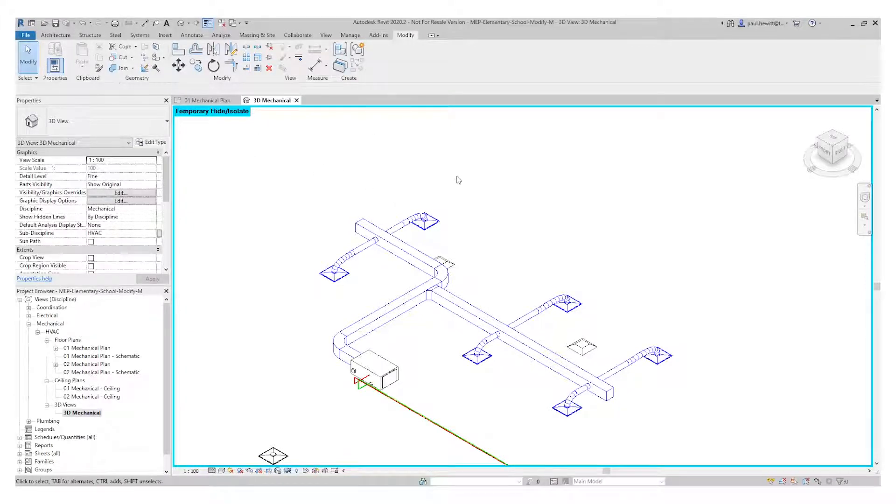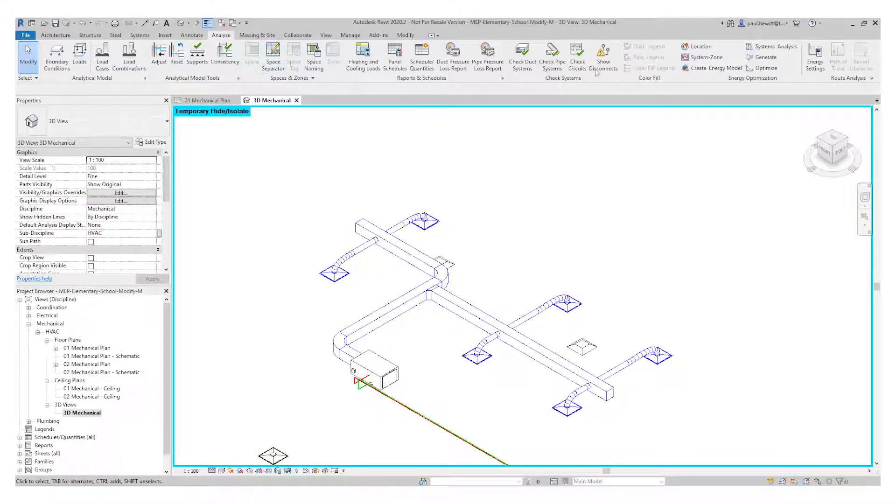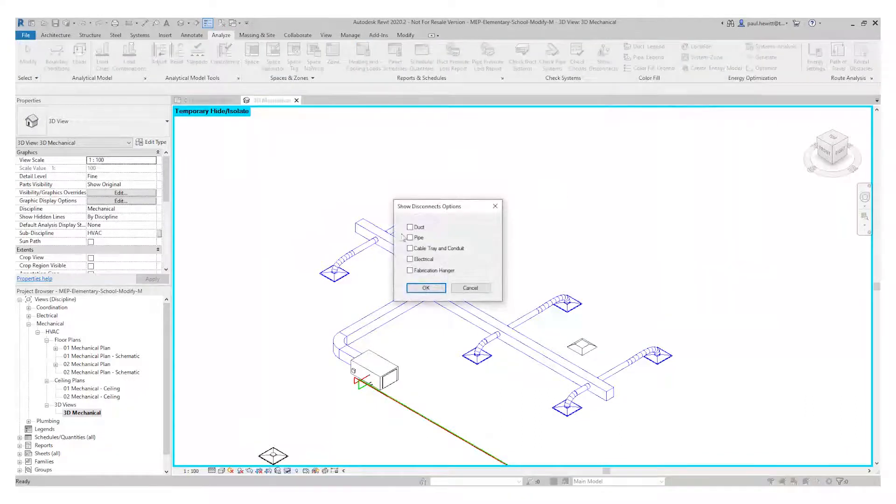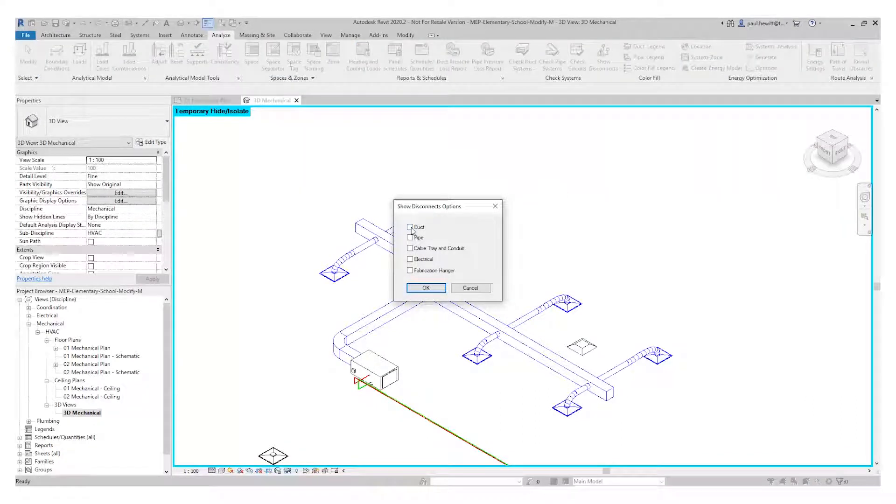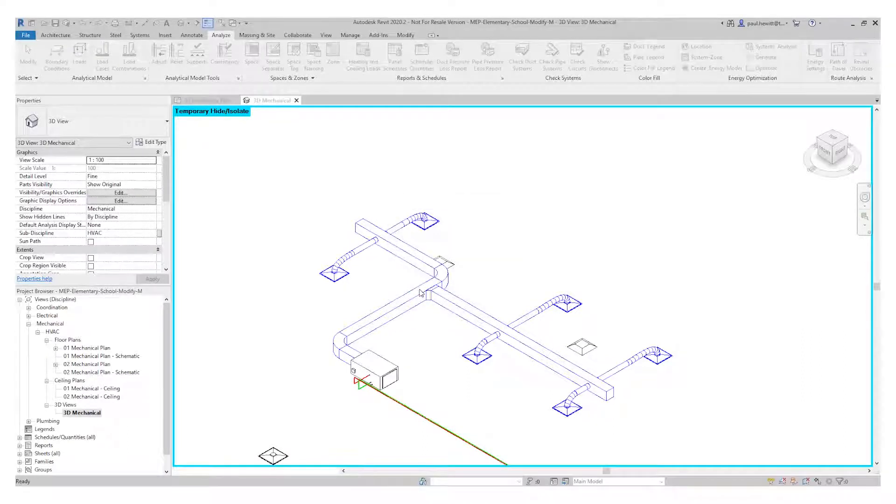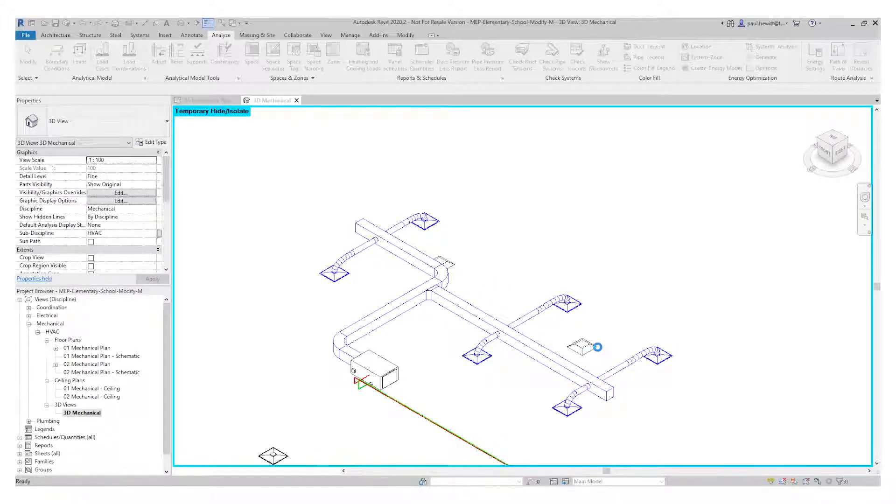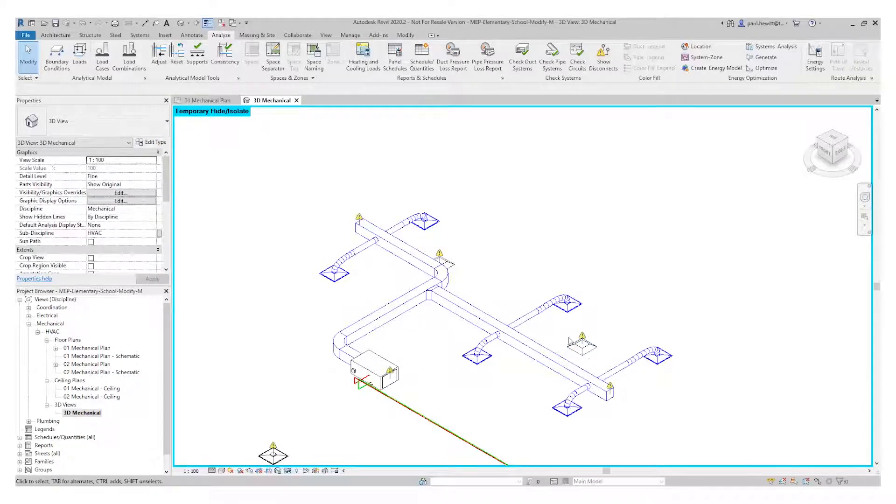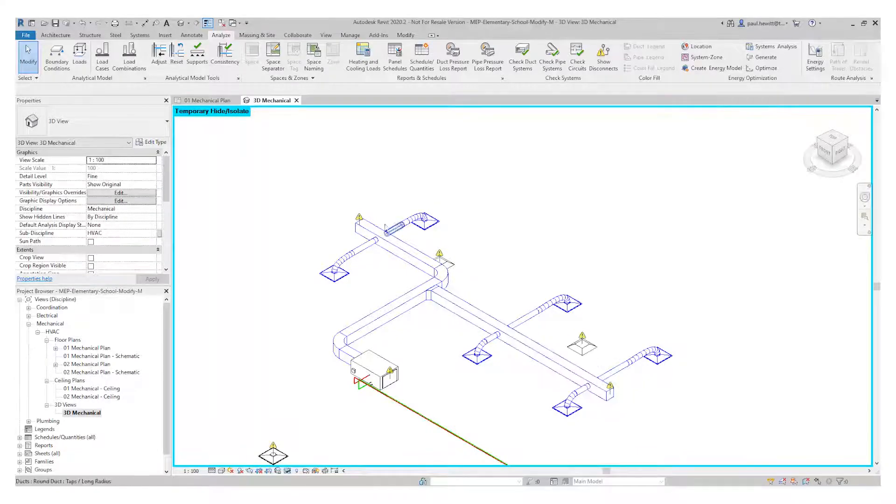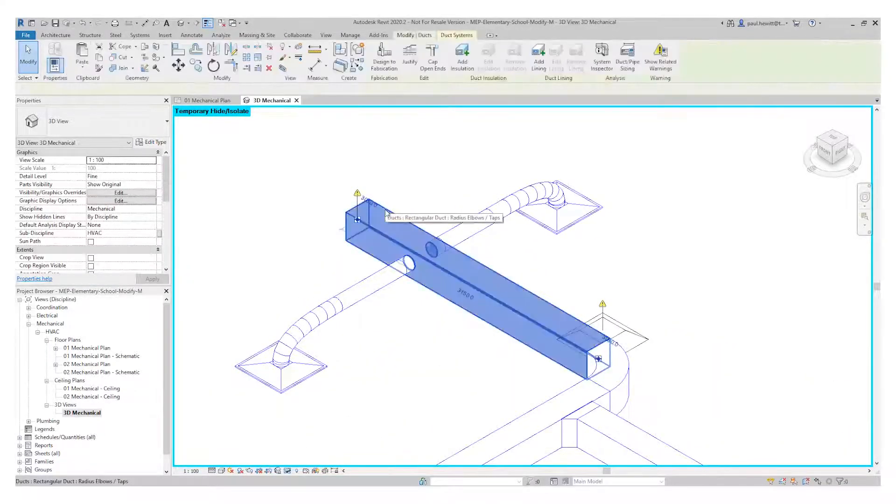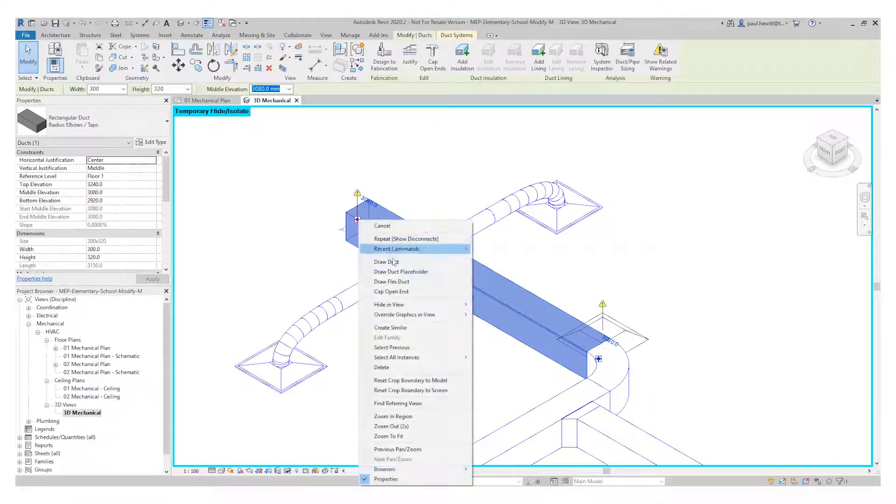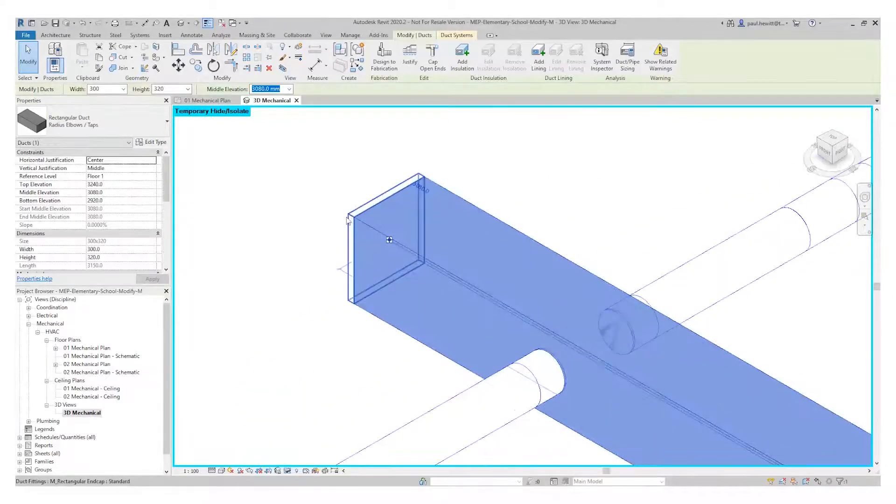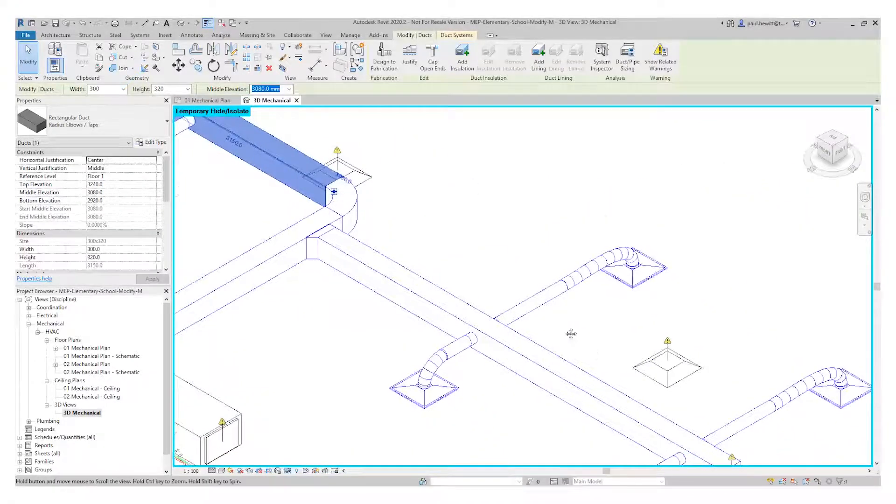So the first thing I need to do is, I want to check if there are any open ends in this particular layout. So I've got, under analyze, I've got the show disconnects. Let's select duct. So it's the duct disconnects I'm after. It takes a couple of seconds because it does the whole model. And you'll find that there are going to be some disconnects for these air terminals here. These are the return air terminals that we haven't connected yet. But we've also got end caps missing. So a couple of things we can do. First of all, with this one I'm going to select the duct, right hand click on the connector, and say cap open end. And now you can see it's capped that lovely for me for the right size.